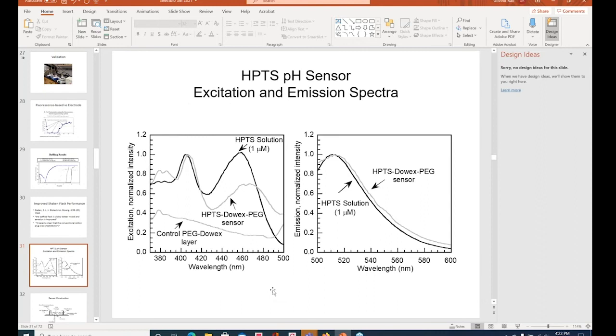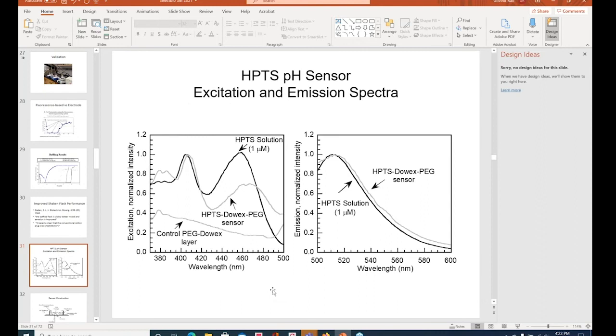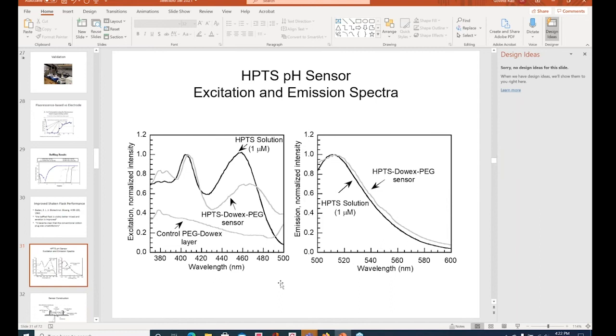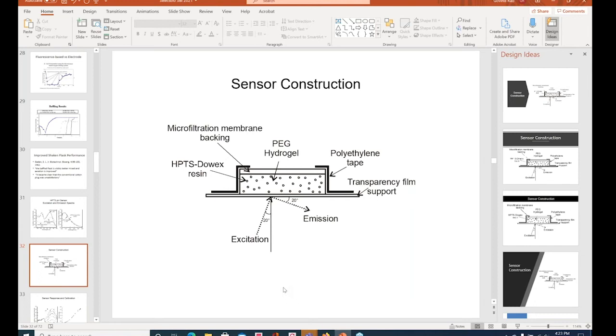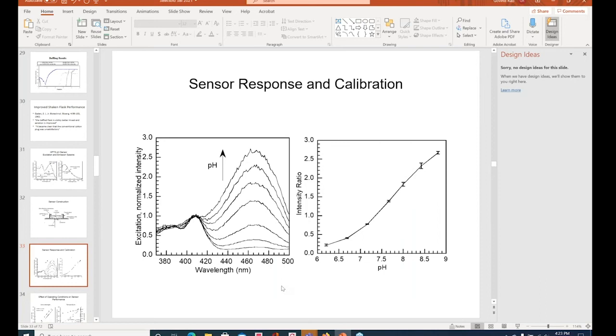Now let's switch gears a little bit and talk about pH. So pH again, HPTS is the dye we use. I think Paul talked about this earlier this morning. And we actually had to figure out how to get HPTS, not in solution, but into a patch. So this was our very first pH patch that was immobilized in a polyethylene glycol hydrogel. And what was remarkable about this is it's basically like a soft contact lens, that we had to figure out how to make it steam sterilizable, because that was pretty much the standard for bioreactors.